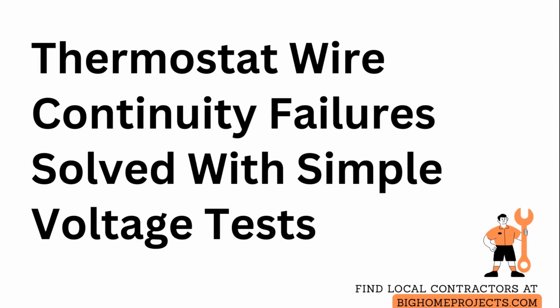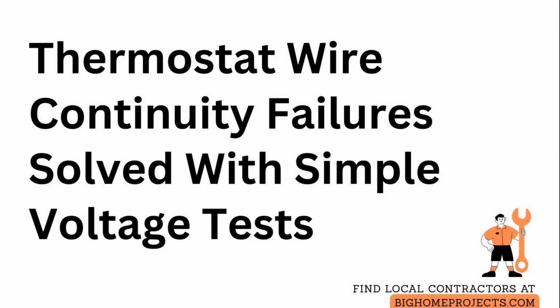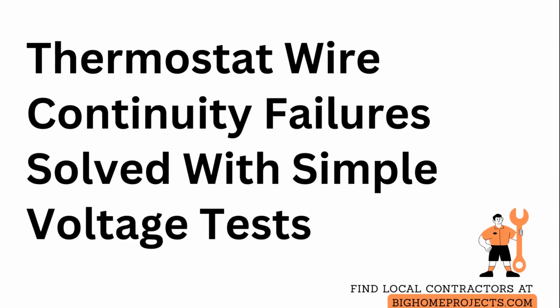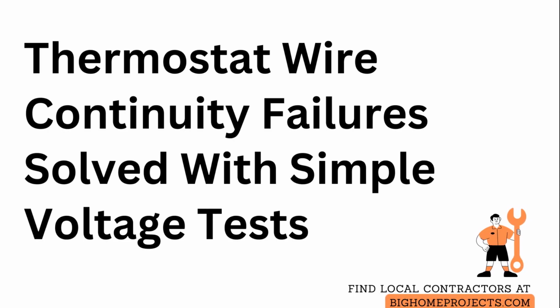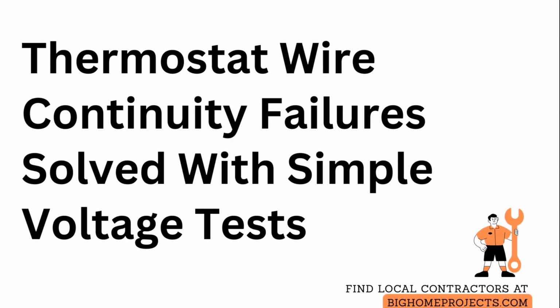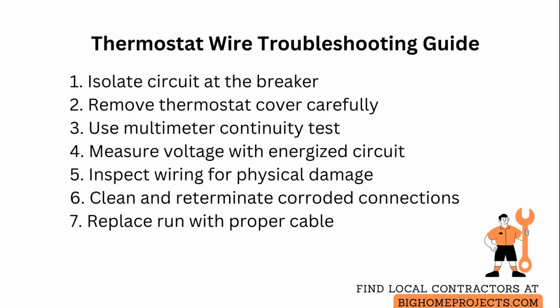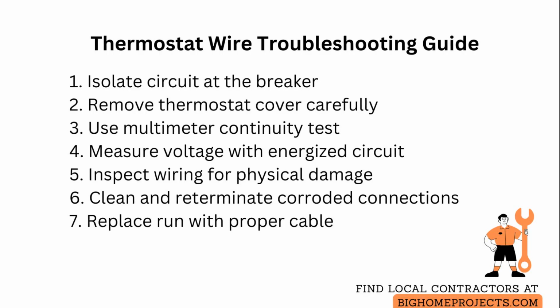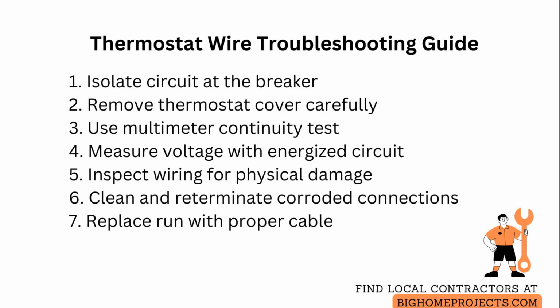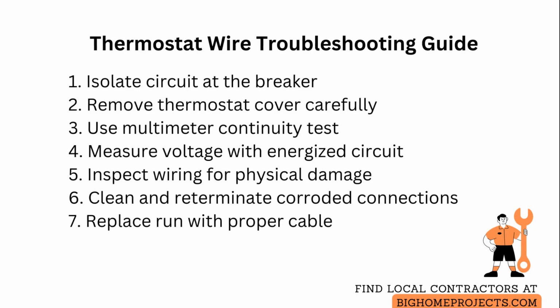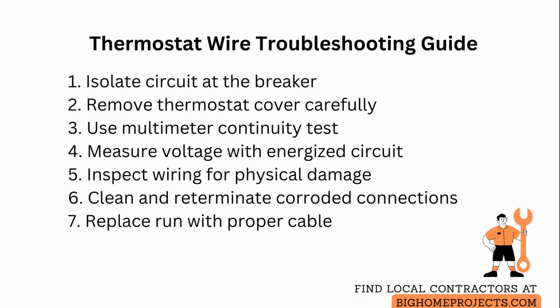A damaged thermostat wire in an older home can indeed cause no voltage at a terminal, and testing continuity and inspecting connections should be your immediate response. Start by isolating the circuit at the breaker and remove the thermostat cover to expose the terminal block. Use a digital multimeter set to the continuity or resistance function to test between the transformer common and each thermostat conductor to confirm continuity. A reading of infinite resistance or open circuit indicates a broken conductor.